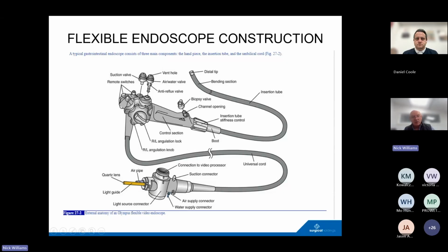On a video scope, you have remote switches, usually for freezing or for taking pictures or for changing the modality of the imaging, that can be used, are programmable. I've already mentioned the angulation knobs here, up, down, and right, left, and there's a lock, because sometimes when you're moving this, you get it how you want it, and you want it to keep it that way, and so there's a lock. This is the lock for that angulation knob, and that's the lock for that one.